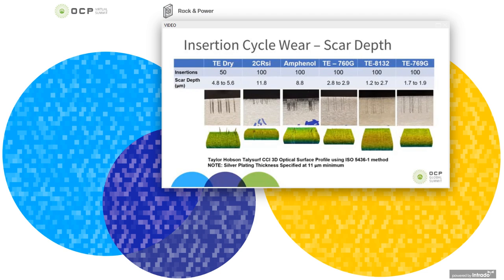scar depth significantly. And then the other thing that you can look at, if you compare TE to 2CRSI and the Amphenol scars, is that the actual scar shape and length is different because of the different contact profile that each of the connectors have. So even though we used the same BusBar, we had different scars on it because of how they contacted the BusBar.